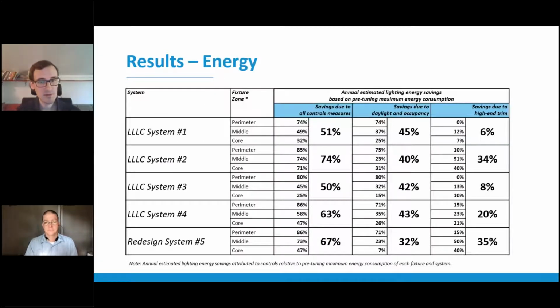I'll just set up this table here for Kevin. What we're looking at is a breakdown by system in the rows, with 3 columns of data. The one on the left looks at savings due to all of the controls measures, which includes daylight harvesting, occupancy sensing, and high-end trim. The middle one looks at only daylight harvesting and occupancy, and the one on the right looks at savings due to high-end trim only.